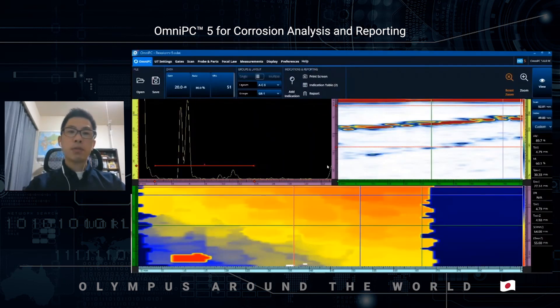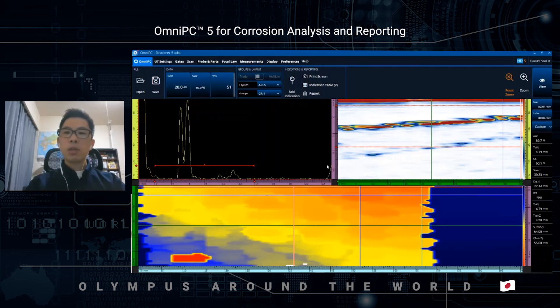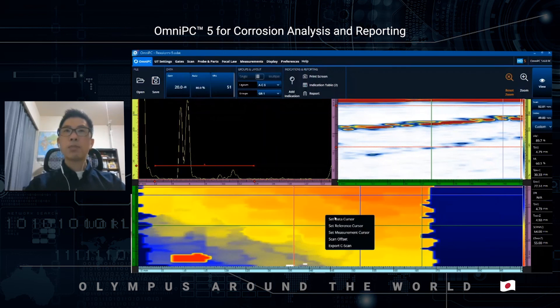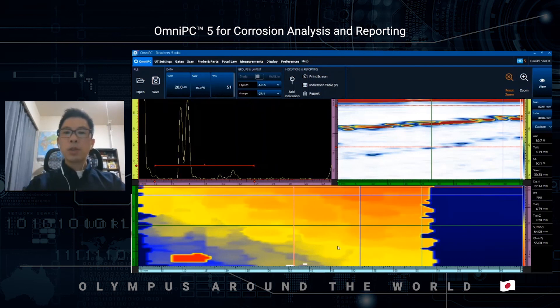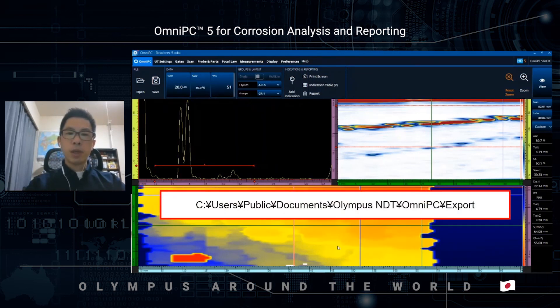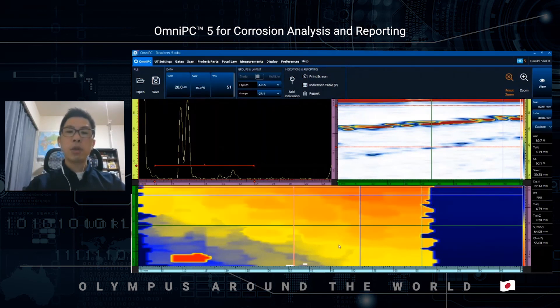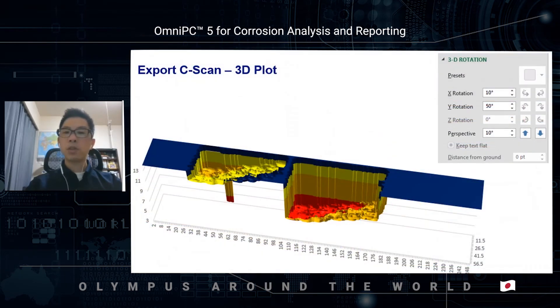If you have your own original report format, or you would like to visualize the C-scan data in Microsoft Excel, you can export the C-scan data as a text file by simply right-clicking on the C-scan and selecting Export C-scan. You will find the exported text file in the export folder, and can create a 3D representation like this. Very easy.